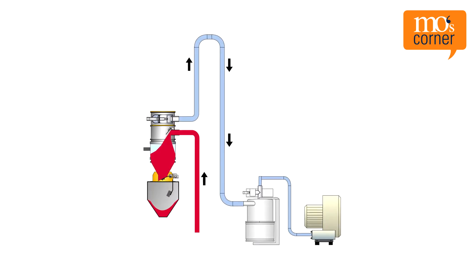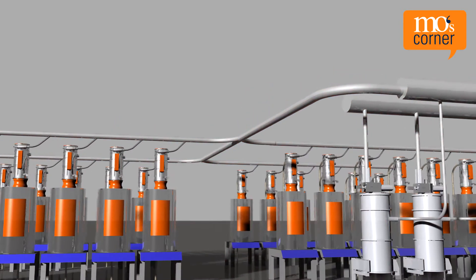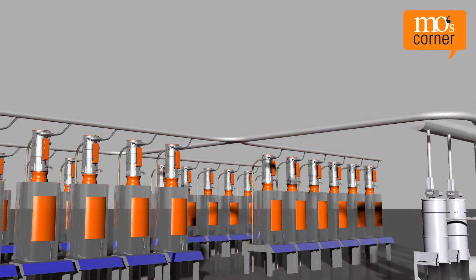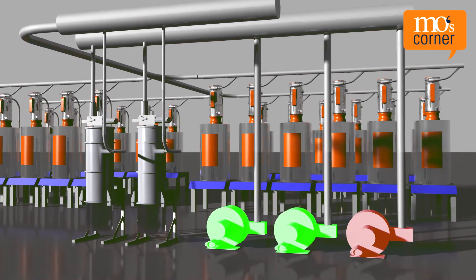What is the advantage of a central vacuum? The pumps' start-up time and run-on time, during which no conveying takes place, is reduced. The more individual pumps work independently at the pace of production, the greater the losses due to start-up and run-on times, making a central vacuum system worth it. The vacuum pumps are controlled automatically, depending on the utilization of the connected devices. An accidentally generated excessive vacuum can be stored in the vacuum lines and is therefore not lost for the complete system. Operational safety: due to the use of several vacuum pumps, a constant vacuum is ensured in the complete system, even in the event of failure of individual elements.